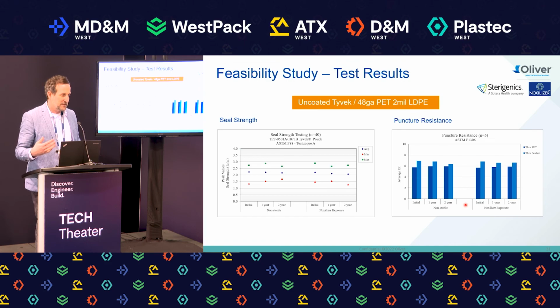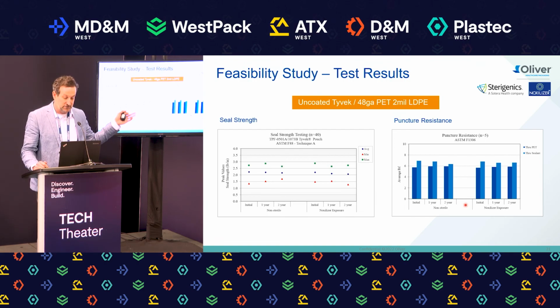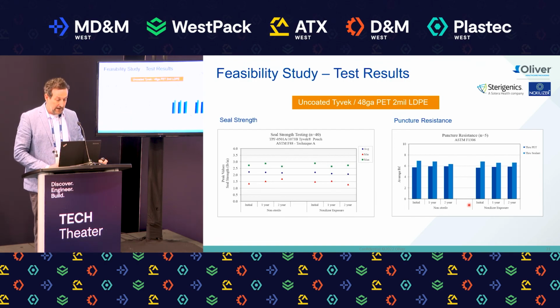So that's one thing, probably the most critical thing we look at with our pouches, and what packaging's kind of measured on in our field is seal strength, and that shows that it performed very well after that worst case sterilization 2-time cycle. And puncture resistance, that's also very important.